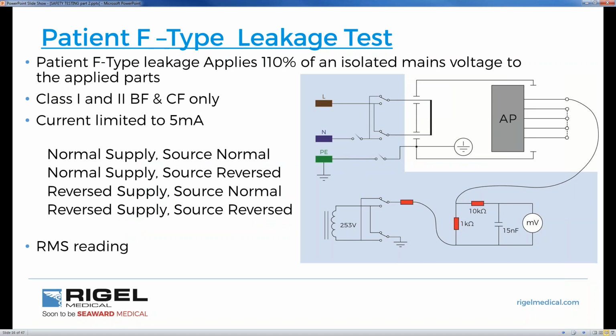Patient F-type leakage, otherwise known as mains on applied part. What we want to check, what we want to satisfy with 60601 design is that, as I've discussed earlier, with the applied part we want total isolation. So we've got conductors coming in that power the device to make sure the device operates in its intended purpose of use. What we want to prove is that if any mains or any voltage can become present on the patient that will be connected to an applied part, we have total isolation so it doesn't flow back to protective earth.